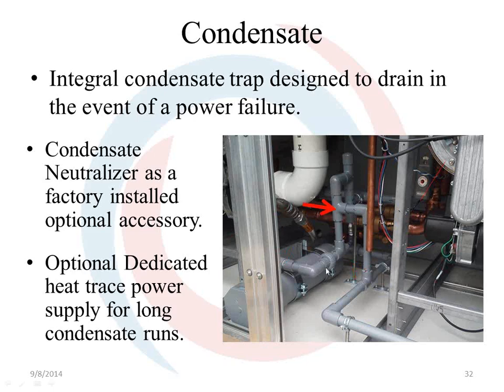There's also a bypass line. You can see the bypass line right here if the condensate neutralizer does get clogged. And the condensate can either be piped out the bottom of the unit or it can go outside the unit itself. This one is showing that the unit is going outside the unit. Now if it goes outside the unit, there would need to be heat traced by others. But one of the other options is also a convenience outlet, so you can plug in any kind of heat trace.